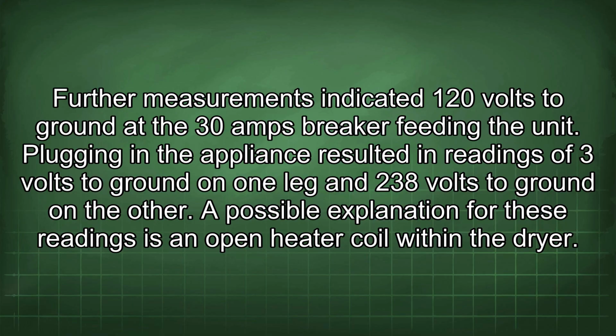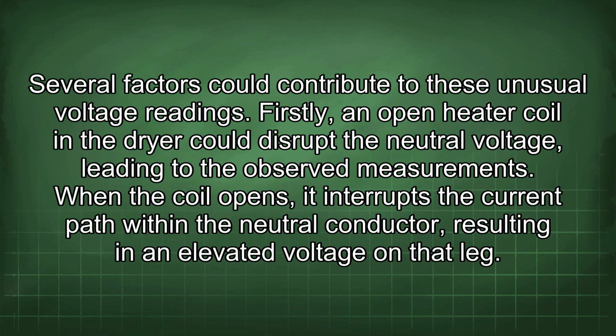Plugging in the appliance resulted in readings of 3 volts to ground on one leg and 238 volts to ground on the other. A possible explanation for these readings is an open heater coil within the dryer. Several factors could contribute to these unusual voltage readings. Firstly, an open heater coil in the dryer could disrupt the neutral voltage, leading to the observed measurements.